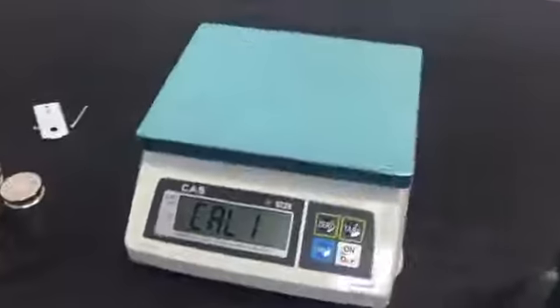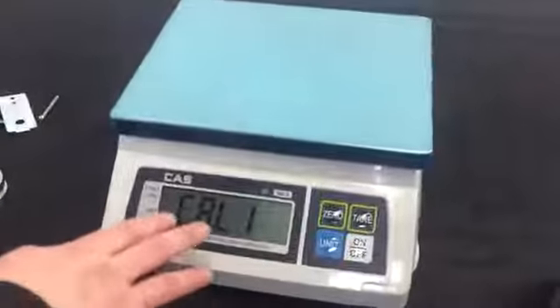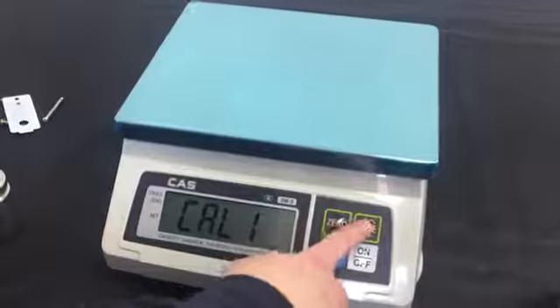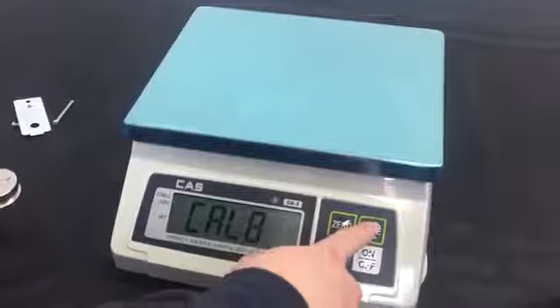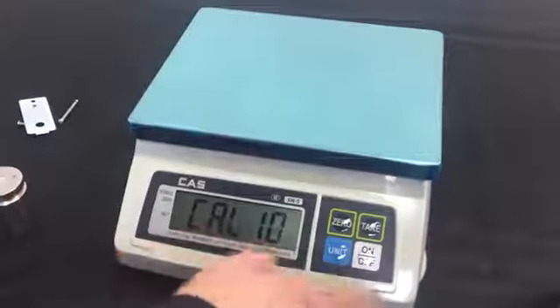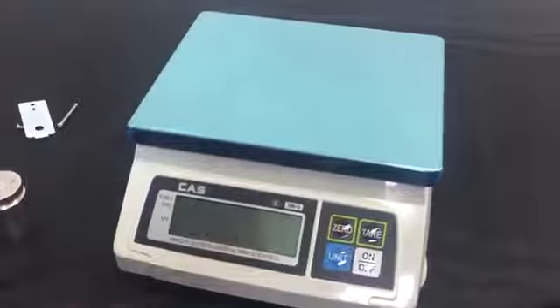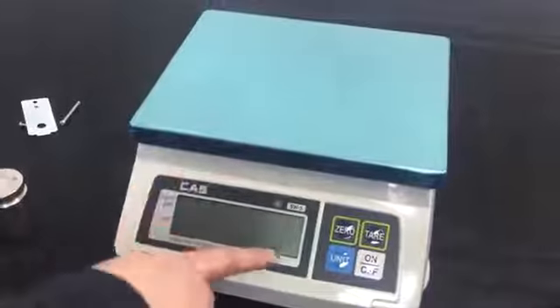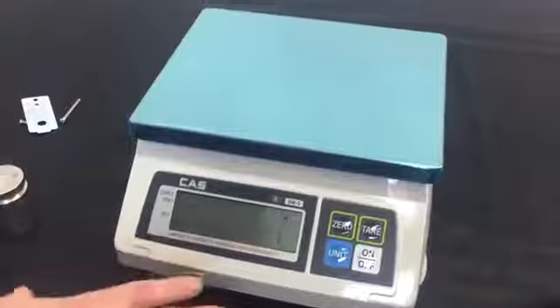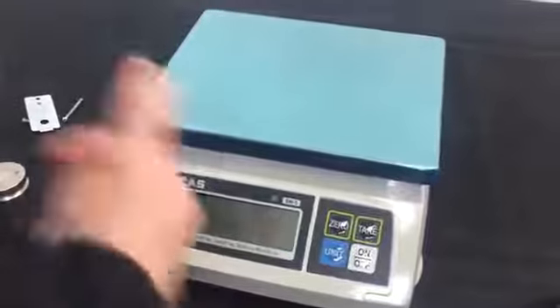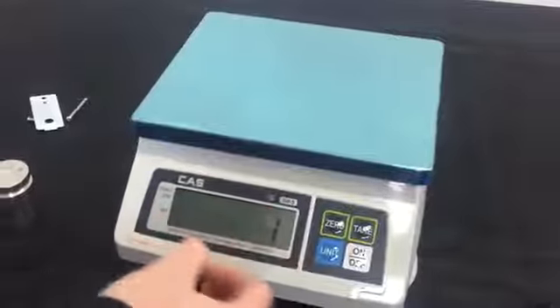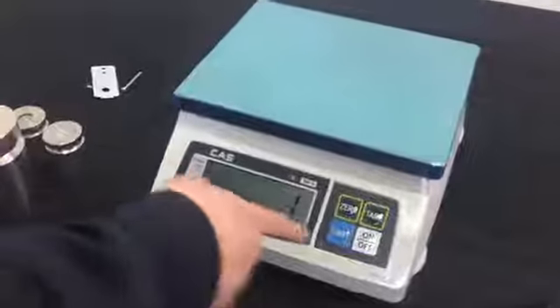All right, now what we're going to want to do first is navigate to Cal 10. You do so by pushing the Tare key until you see Cal 10 on your display. In order to enter into the setting, press the 0 key. Now it says unit and 1 is flashing. 1 is for pounds, which is good. We want to calibrate in pounds today. Make sure that you know which type of scale you're working with, your SW, to know whether it's kilograms or pounds. 0 is for kilograms, 1 is for pounds.